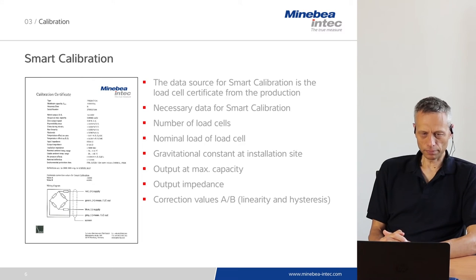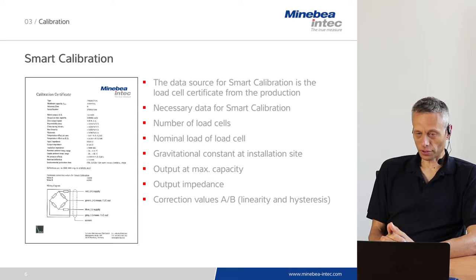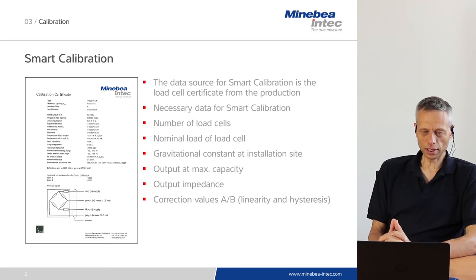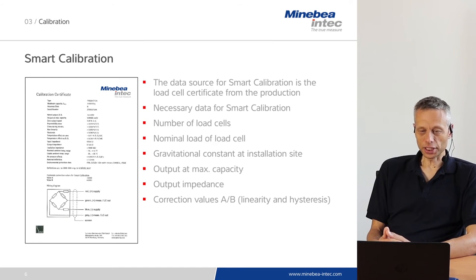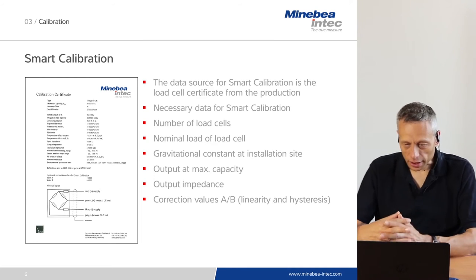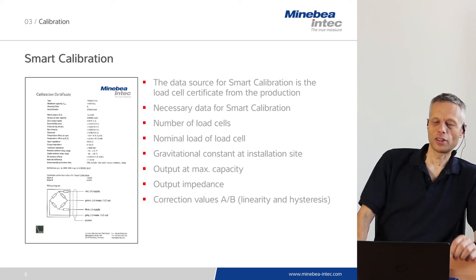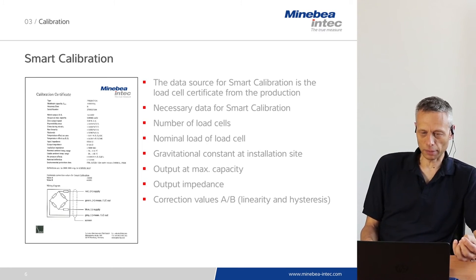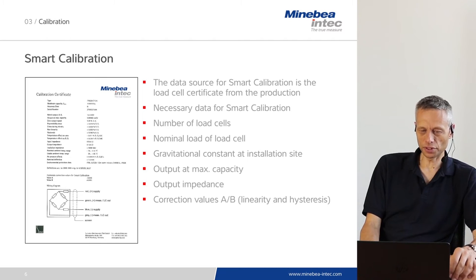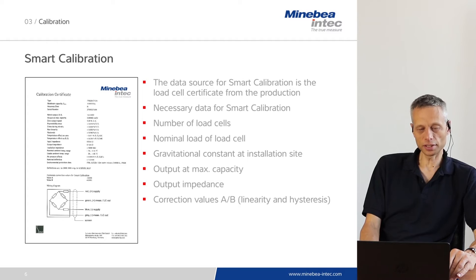This is a load cell certificate here. It contains all necessary data for the smart calibration, such as the number of load cells, the nominal load of each load cell, the gravitational constant at the installation site, the output value at the maximum capacity of the load cell, the output impedance, and individual correction factors for linearity and hysteresis.